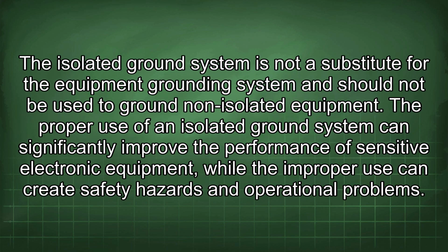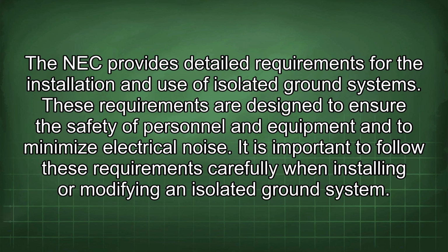The isolated ground system is not a substitute for the equipment grounding system and should not be used to ground non-isolated equipment. The proper use of an isolated ground system can significantly improve the performance of sensitive electronic equipment, while the improper use can create safety hazards and operational problems. The NEC provides detailed requirements for the installation and use of isolated ground systems. These requirements are designed to ensure the safety of personnel and equipment and to minimize electrical noise. It is important to follow these requirements carefully when installing or modifying an isolated ground system.